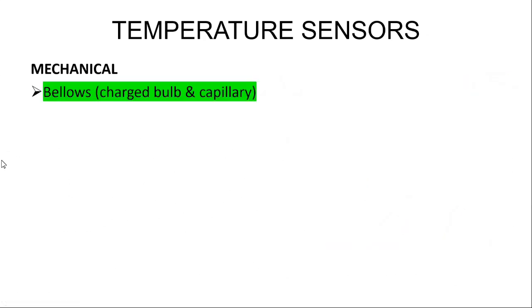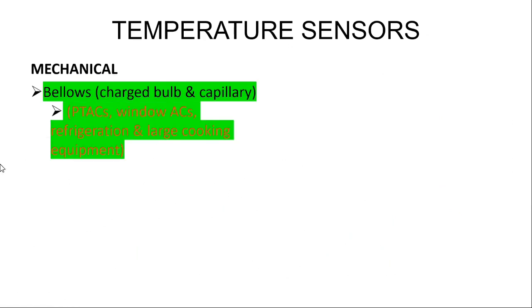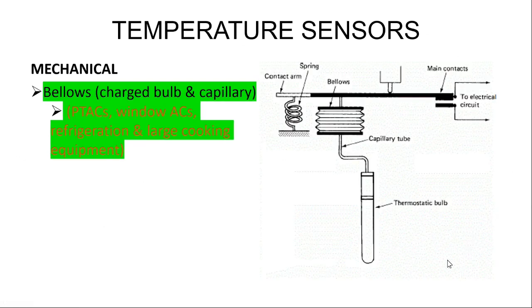Another type of mechanical control is a bellows, which is a charged bulb and capillary. These are used in package terminal air conditioners, window air conditioners, refrigeration, and large cooking equipment. So in this illustration, you have your bulb, you have your capillary, and then you have a bellows. I should probably add that it's also charged with the same gas. Up here you have the contact arm.